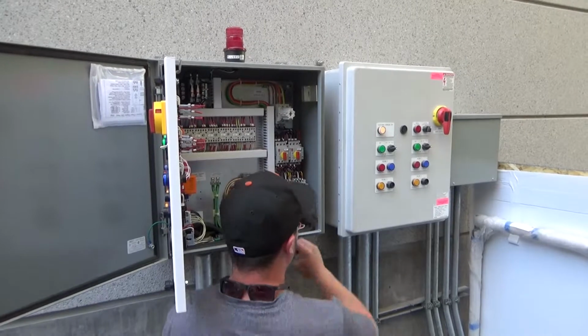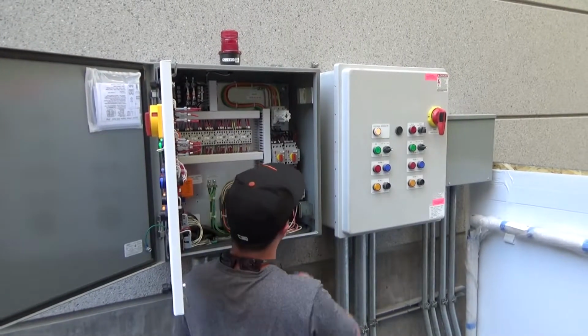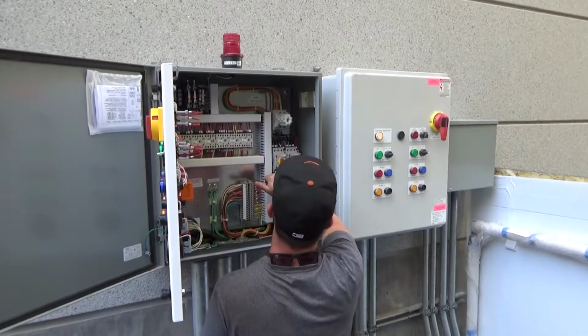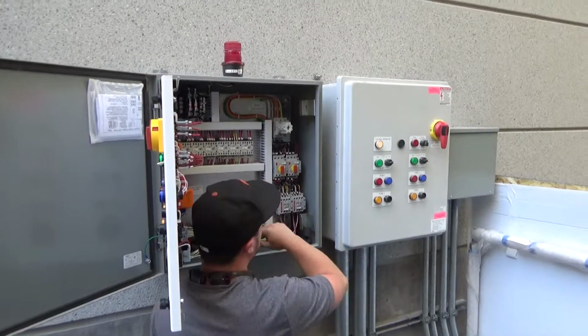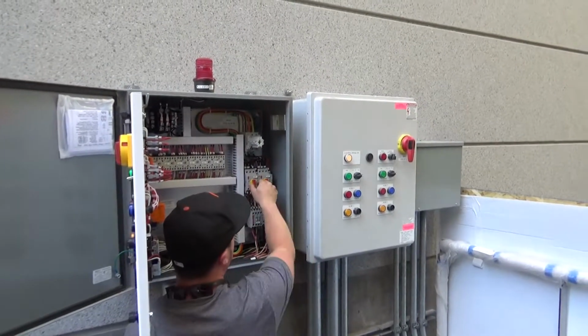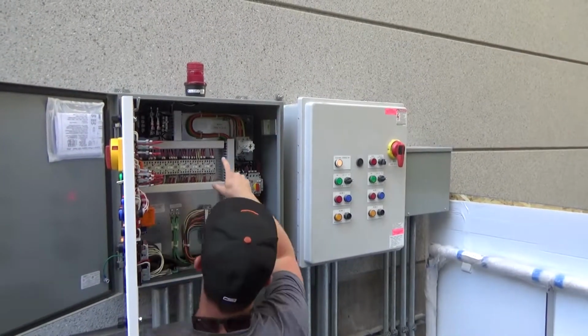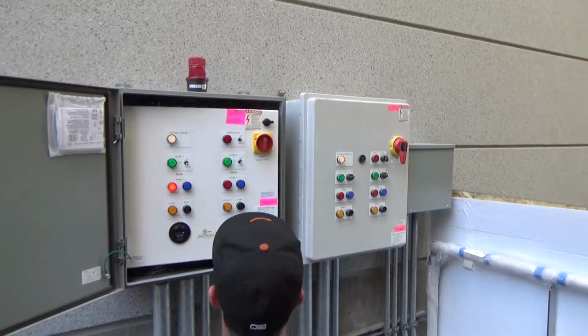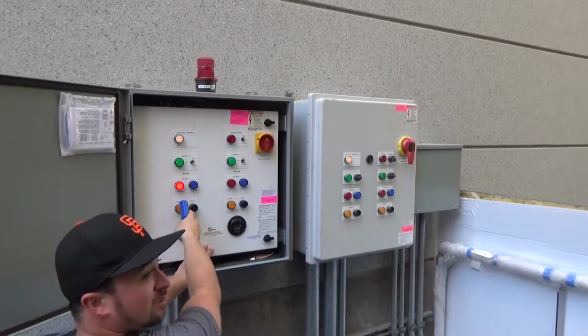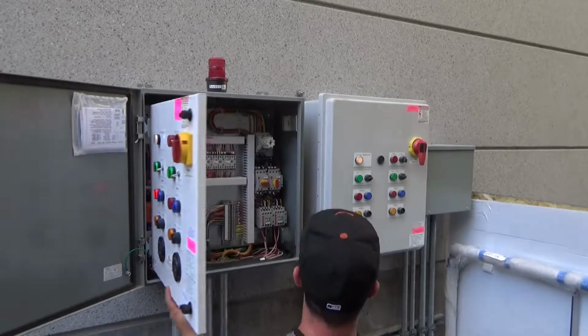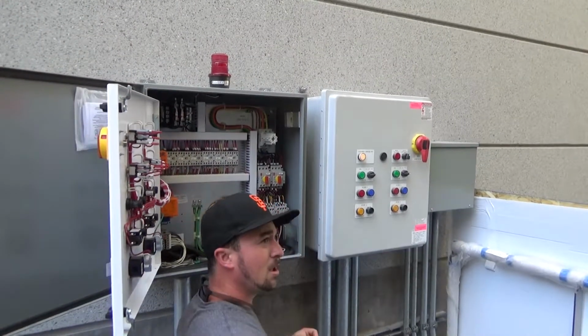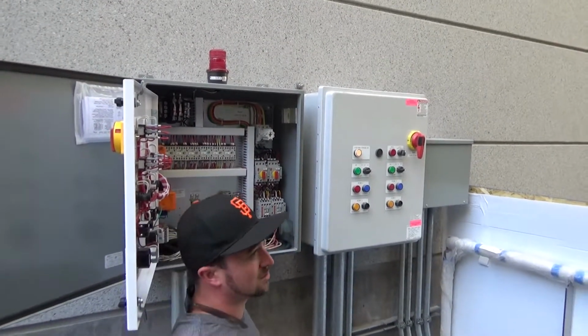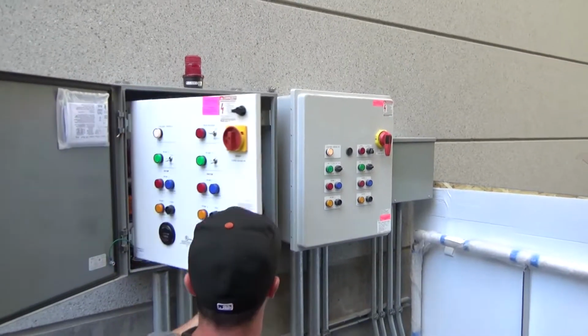Correct. Okay. So say I'm pulling way too much. We have it set at like 8 amps, okay? So I pull like 15 or something like that. I trip, all right? It's going to let me know on the front too. So someone's going to have to come and reset it. But if it tripped, there's something else that needs to be looked at. Further investigation needs to be taken.